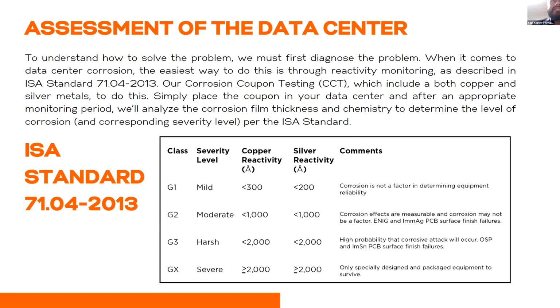As per standard, the ISA standard says that G1, G2, G3, GX are the grades which need to be maintained in the data centers. G1 is the mild grade, which practically all facility managers have to maintain. G2, G3 are the above conditions where failure will happen.